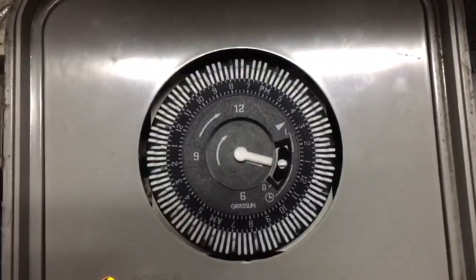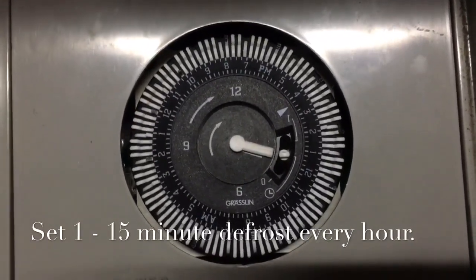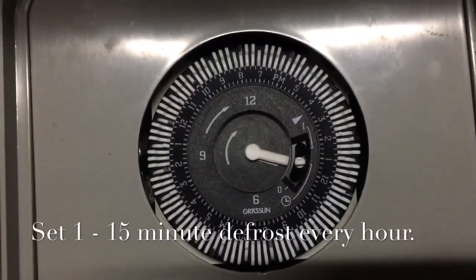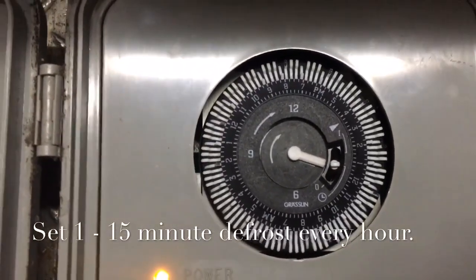We've got some pretty good temps in here now. This works real good. They're defrosting every hour for 15 minutes. The machine runs maximum 45 minutes and then shuts off for an hour defrost on a messed-up coil. It's a good setup — the coils just kind of mess up, but that setup works real good.